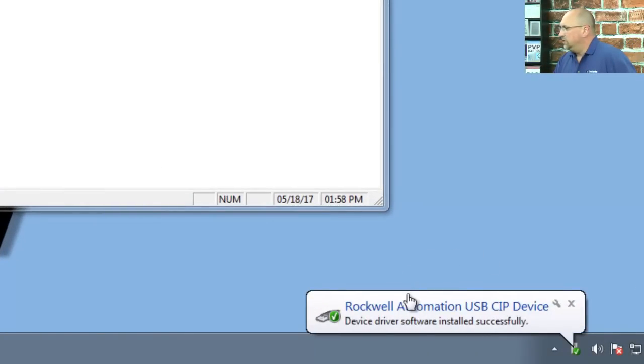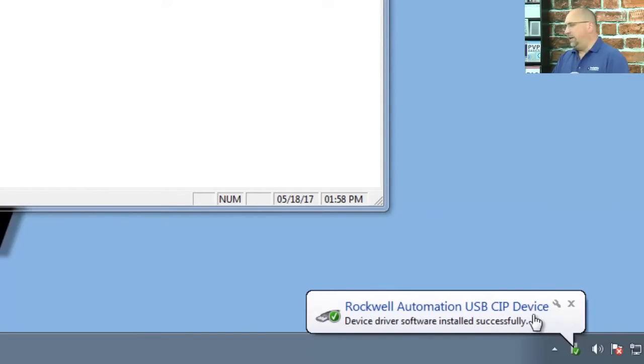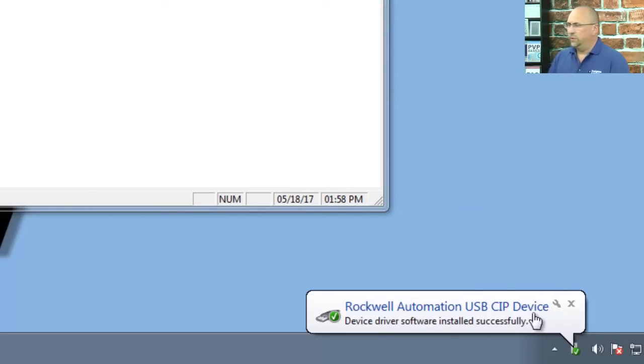Now if we come over to the PC, you'll notice down here at the bottom that Windows is installing the Rockwell Automation USB CIP device driver. If that doesn't install automatically, it can be because you have an old version of RSLinx — old versions won't have the drivers for new operating systems or maybe not the latest 64-bit driver. If you have the latest version of RSLinx, you typically won't have a problem with that installing.